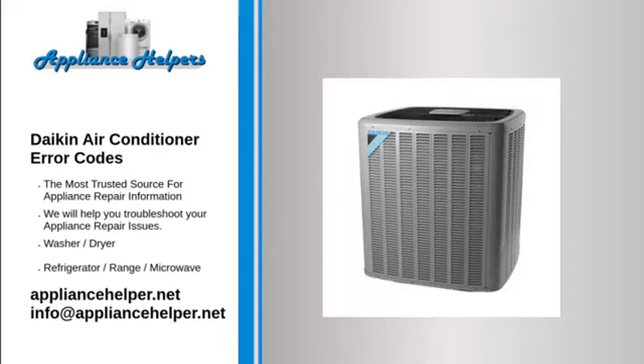Code C4. Problem: malfunction of liquid pipe thermistor for heat exchanger. Defect of connector contact. Defect of liquid pipe thermistor for heat exchanger. Code C5. Problem: malfunction of gas pipe thermistor for heat exchanger. Defect of connector contact. Defect of gas pipe thermistor for heat exchanger.